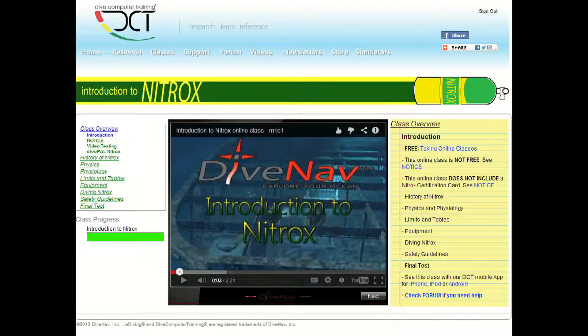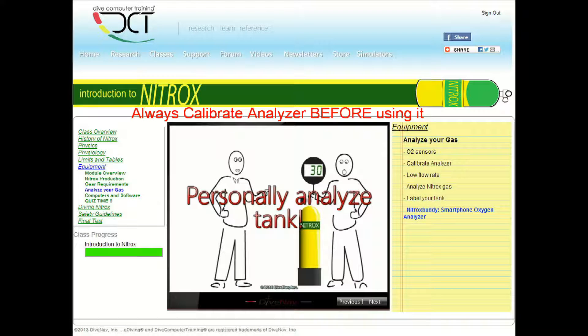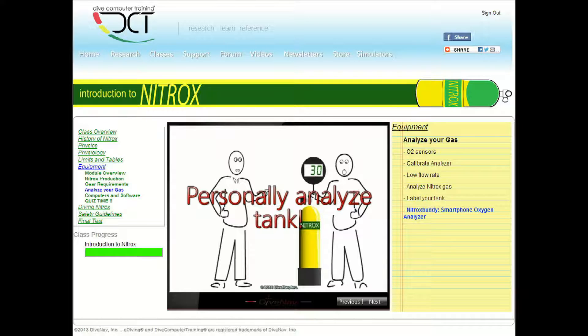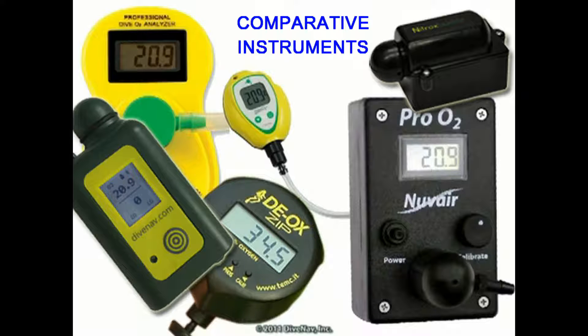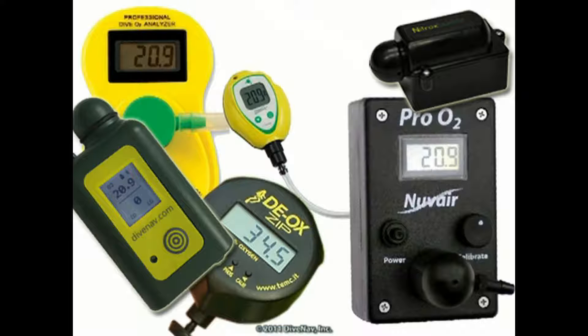When you took your Nitrox class, you learned that you must always calibrate an oxygen analyzer before using it. This is because oxygen analyzers are comparative instruments and not absolute instruments.